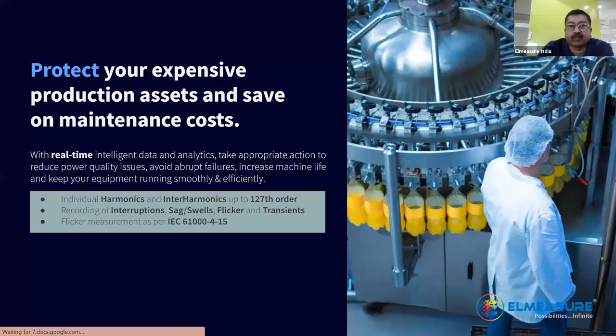And the power quality reporting is as per EN 50160. It's a European norm which talks more about voltage harmonics, voltage imbalances and so on, but we are going further by giving other parameters also. Coming back to the harmonics in the product, the display can go up to the 60th harmonic, and in the system, we give software, along with which you can get data up to the 127th order in both individual harmonics and interharmonics. Then you can have recording of interruptions, sags, swells, flicker and transients, as well as flicker measurement, which is as per IEC 61000-4-15.